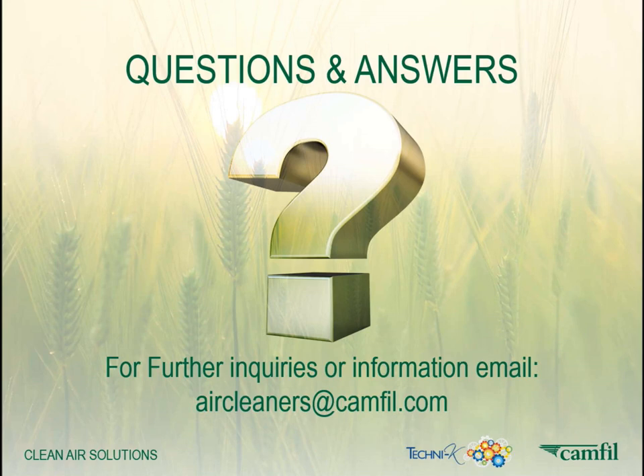Getting specific here, what class of filter would you recommend for a hatchery? Any suggestions? I would recommend, at a very minimum, an ePM1 50% for a hatchery. What sort of conditions are we talking about there that need to be taken into consideration? Ultimately, the conditions you're talking about is the indoor air quality. So you want to provide an acceptable level of indoor air quality for the hatchery, at a very minimum in accordance with the BRC standards, with the PM1 50% filter. So all the time it's about adhering to standards, of course.